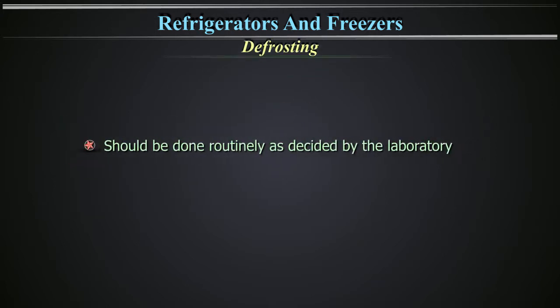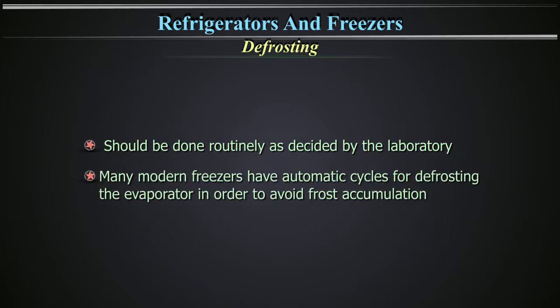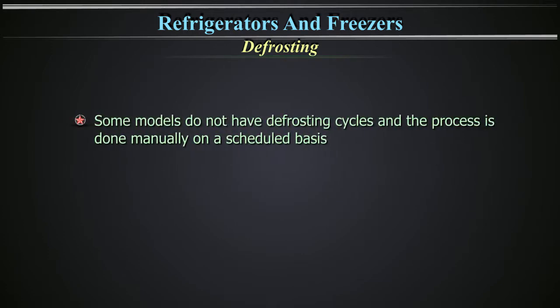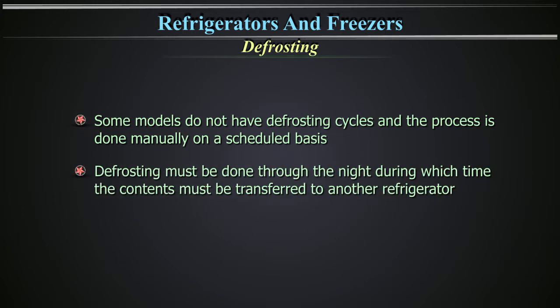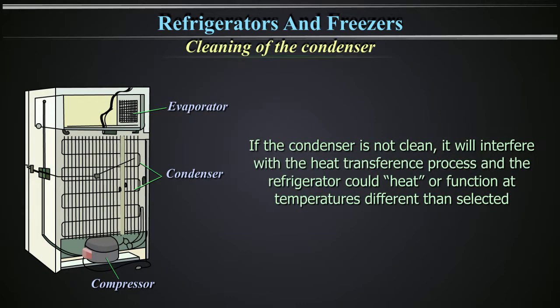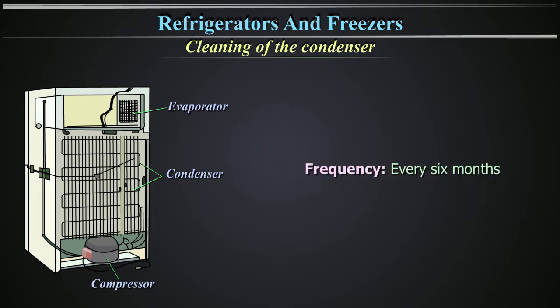Defrosting should be done routinely as decided by the laboratory. Many modern freezers have automatic cycles for defrosting the evaporator in order to avoid frost accumulation. Some models do not have defrosting cycles and the process is done manually on a scheduled basis. Defrosting must be done through the night, during which time the contents must be transferred to another refrigerator. Condenser cleaning frequency is every 6 months.